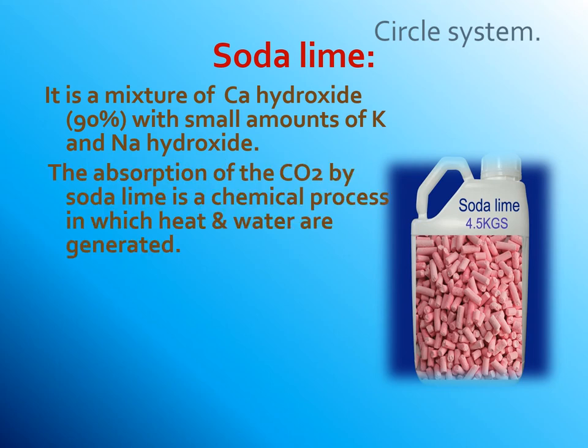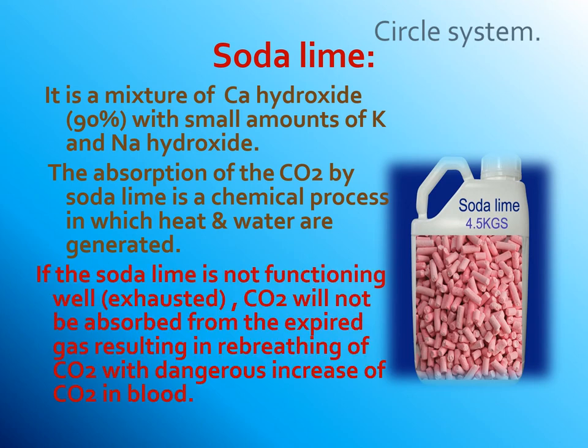Soda lime is a mixture of calcium hydroxide (90%) with small amounts of potassium and sodium hydroxide. The absorption of carbon dioxide by soda lime is a chemical process in which heat and water are generated. If soda lime is not functioning well or is exhausted, carbon dioxide will not be absorbed from the expired gas, resulting in re-breathing of carbon dioxide with a dangerous increase of carbon dioxide in the blood.